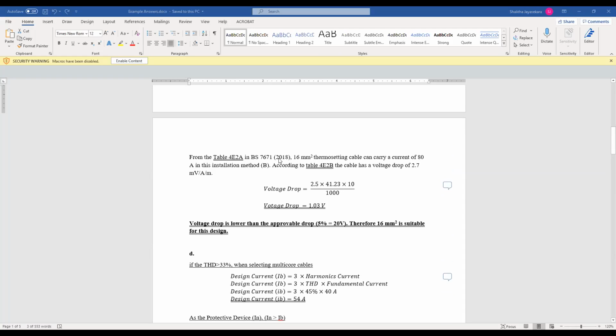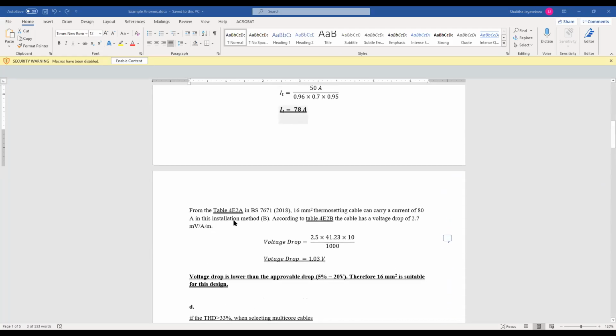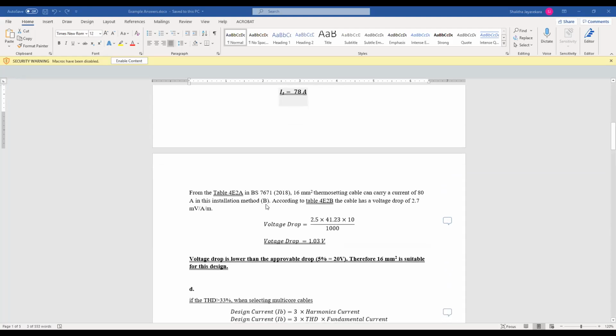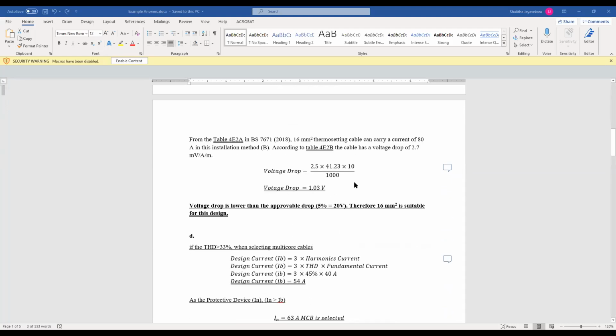16 millimeter square cable will be sufficient to carry 78 amps, but we need to also check the voltage drop. So according to the voltage drop table, usually it is the next table. So if this is 4E2A, your voltage drop table will be 4E2B. So voltage drop you can calculate easily. So you guys have already done this in the mid semester exam also. It will be less than 5%. So usually for three phase 5% is 20 volts. So remember this. Okay, so our rated three phase voltage is 400 volts, and 5% of that will be 20 volts.